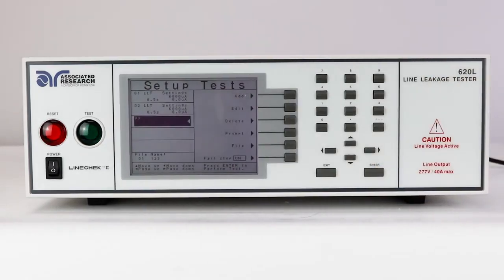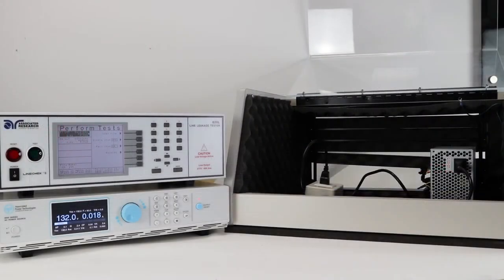In the video, we have set up an earth leakage current test under normal conditions, followed by an earth leakage current test with an output neutral fault. We will be using the IEC 60950-1 measuring device. Next, we're going to connect an external power source to the LINECHEK. This will allow you to run power through the LINECHEK to power up the DUT during the line leakage testing. Then, we'll connect the LINECHEK to the DUT and run a test sequence.